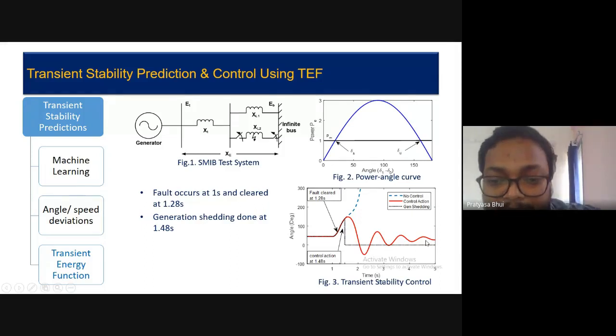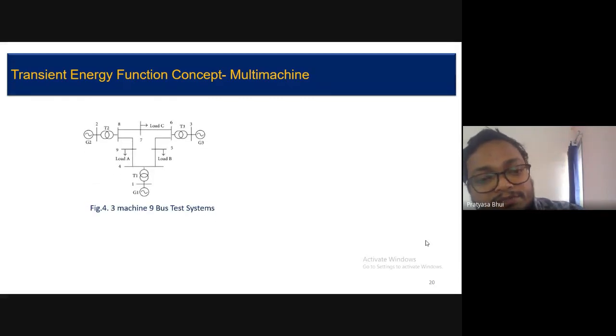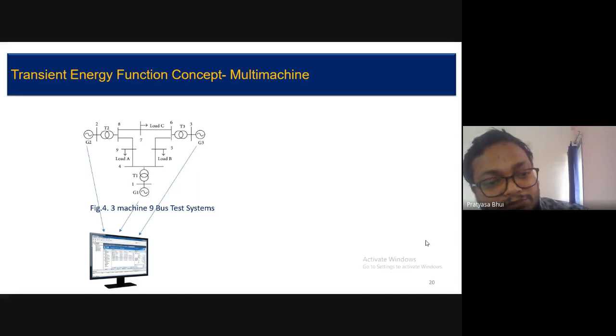So in a generating plant, you may have, say, 5 units or 10 units of, say, 200 megawatts each. So you can shed some of the generation, meaning you can trip some units. If you have 5 units, you can trip 2 units. So this is a 3-machine 9-bus system, and as we discussed, at present we are installing PMUs at all high voltage buses, including the generating plants. So we will get the data in real time at the control center, and then we will predict whether it is stable or unstable. If it is unstable, then we will send the control signal to the generating plant.